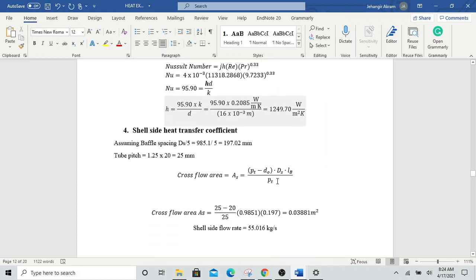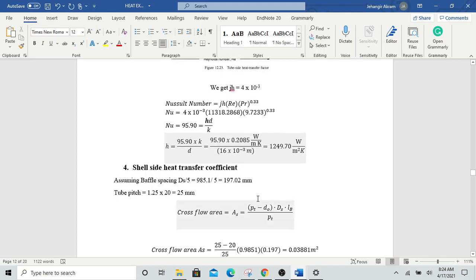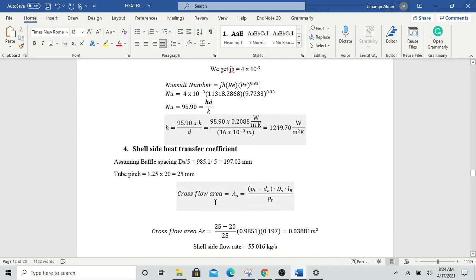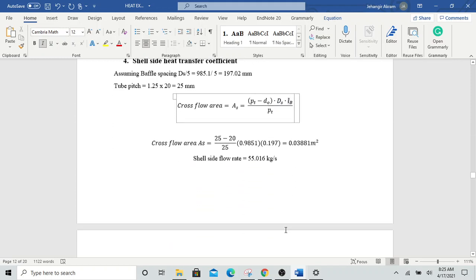In the same manner you can also calculate the shell side heat transfer coefficient, but there is a slight difference, okay. What is the cross flow area in shell? You see, it is not basically the complete area of the shell. There is a tube bundle inside it which is reducing its area, okay. So what will be the area of the shell?